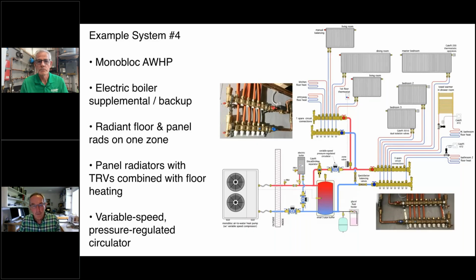And one thing I will point out before leaving it, if you look at these, you notice that the circuits go up and the air vent always has to be up. This is called an inverted manifold. And when you order the manifold from Caleffi, you'll see in the catalog that a standard configuration is with these circuits pointing down, air vent up, but in the inverted manifold, the circuits point up and the air vent points up. And over there, there's the zone valve that controls the flow to that one manifold.